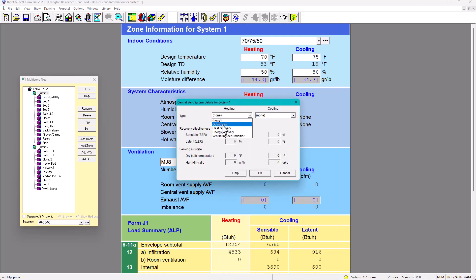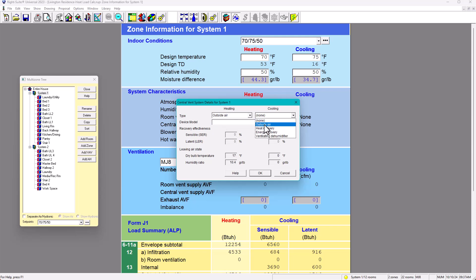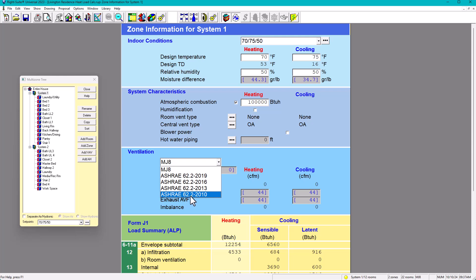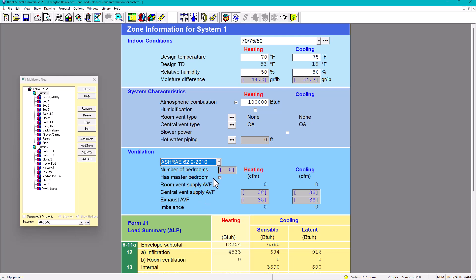For central ventilation, set it to outside air. You have options including ERV or HRV — in Canada, HRV (heat recovery ventilator) is typically used. For the ventilation standard, this is very important as it will bring a lot of load. We'll use ASHRAE 62.2. The 2010 standard is an option, but let's consider a newer version.